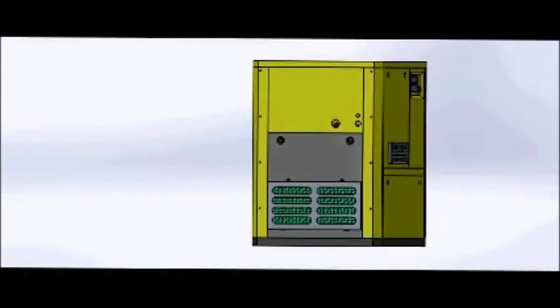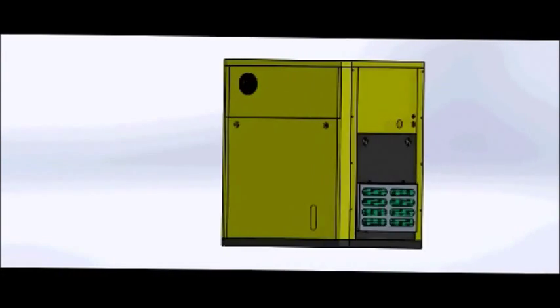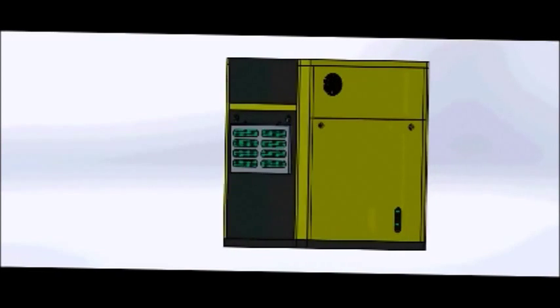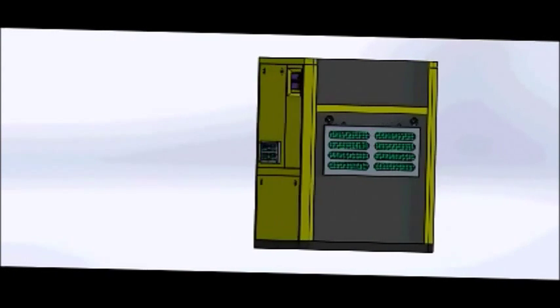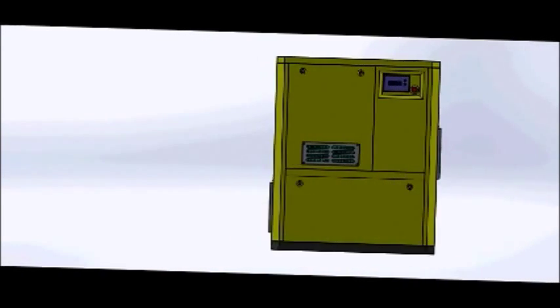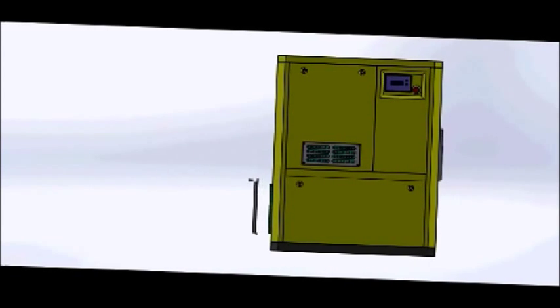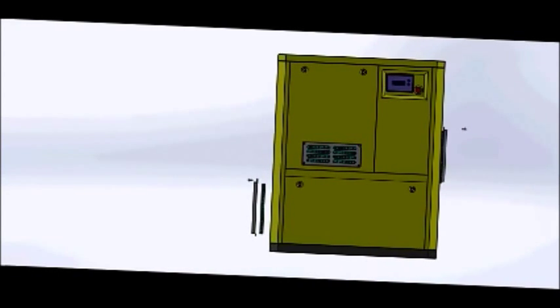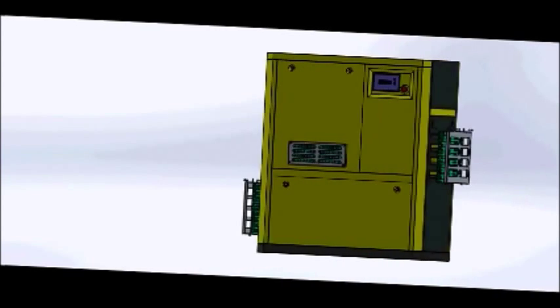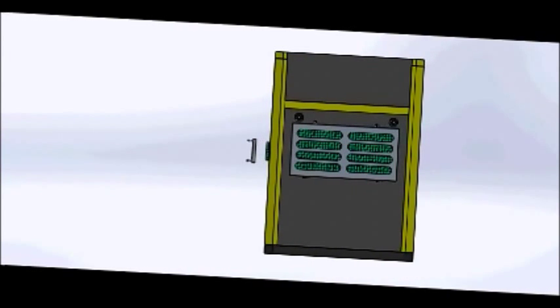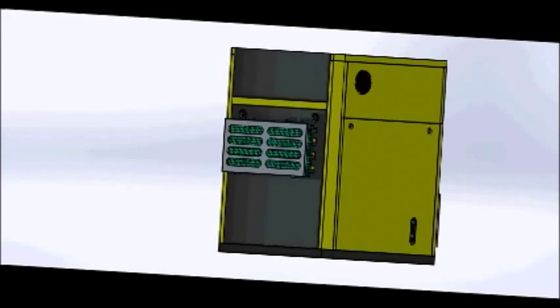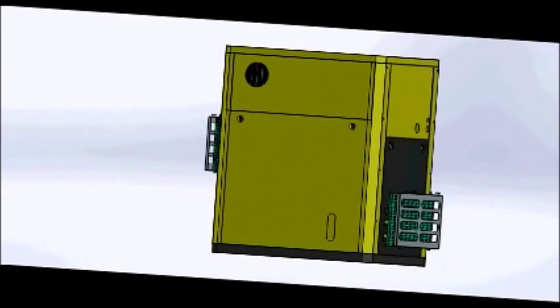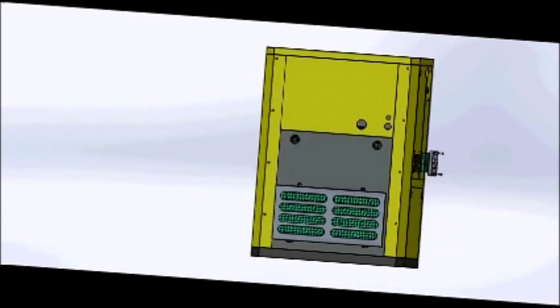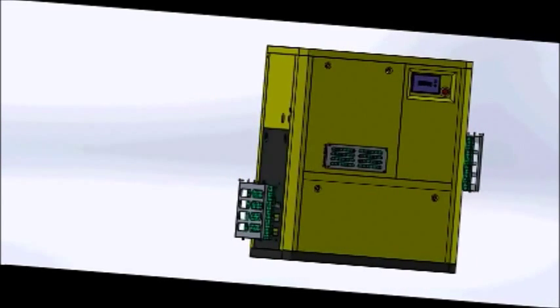Even in the cleanest of shops, inlet cooling air is littered with fine dust and debris that over time accumulates on key compressor components, degrading their cooling efficiency. The most notable component impacted by dirt buildup is the compressor oil cooling and compressed air aftercooling radiator. The dirt buildup serves as a barrier, inhibiting the radiator to work in the manner in which it was designed.